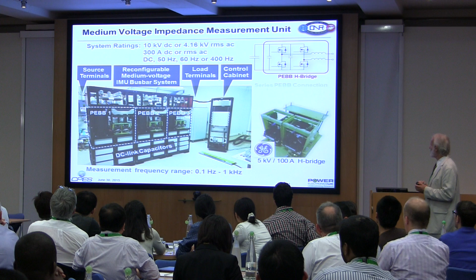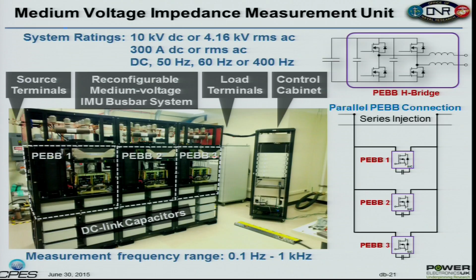They could be reconnected and reconfigured by this system on top. At the bottom, we have DC capacitor banks to inject perturbations at very low frequencies, like 0.1 hertz. Then by reconnecting here, we have these PEBBs, power electronics building blocks, connected in series for higher voltage line to line for shunt injection, when you inject relatively low currents but need to withstand high voltages. For series injection, you need to withstand low voltage but have very high current, since the whole system current goes through you, and you can reconnect those to work in series.